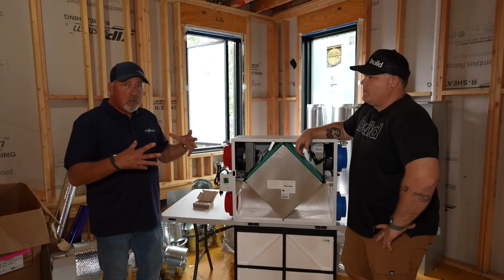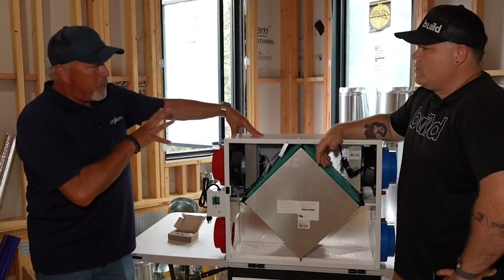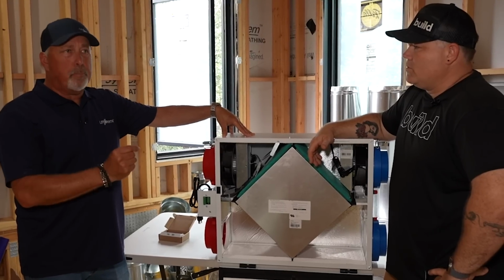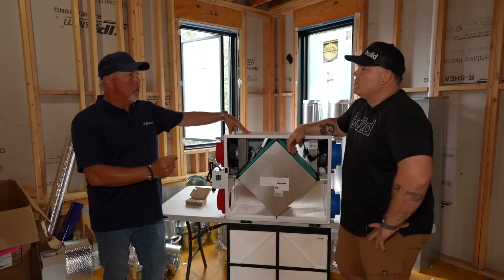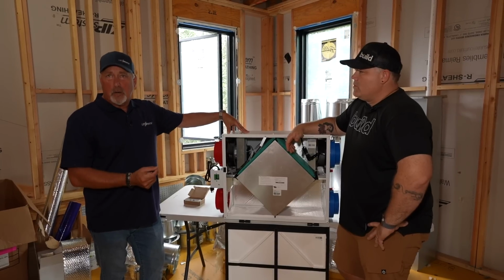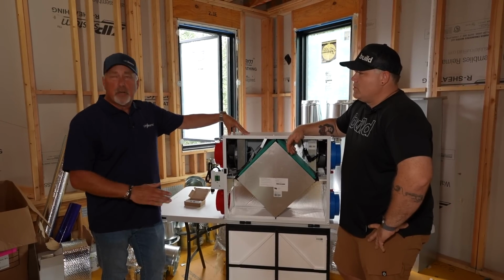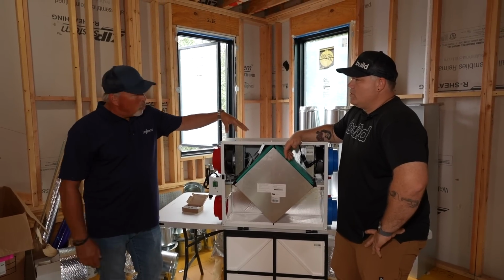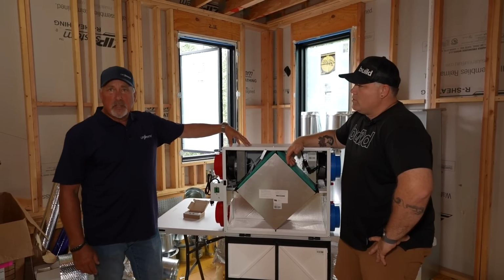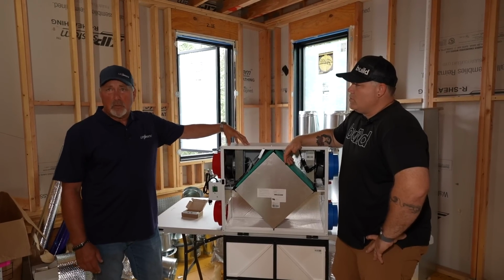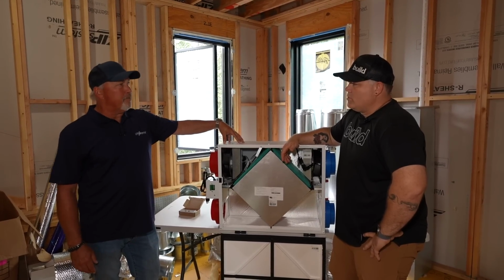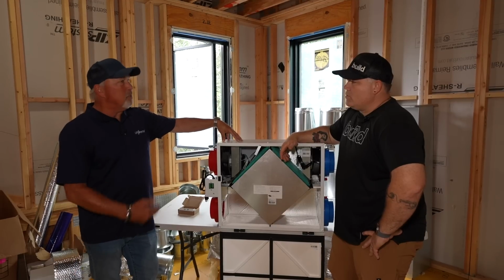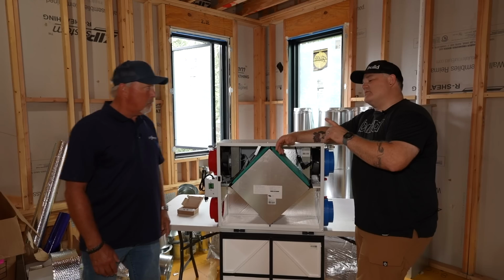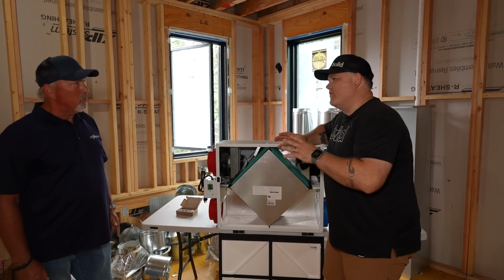Yeah, because nothing's coming in, you've got full control. We are injecting fresh air into the building 24/7, so we're always getting our fresh air. That's important because it's not coming in anywhere else. When these are set up, we set them up for the occupants in the space, so you're getting exactly the right amount of fresh air that you need. Okay, so the key thing you said there was exactly the right amount of air.